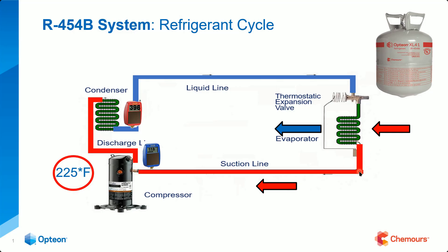It comes down here and the first job of this suction gas — this low superheat, low pressure superheated vapor — is to cool the compressor, because 99.9% of compressors out there are refrigerant cooled. Very few of them anymore are air cooled. I can think of the Copeland K-body. The suction gas comes across that motor and picks up that heat.